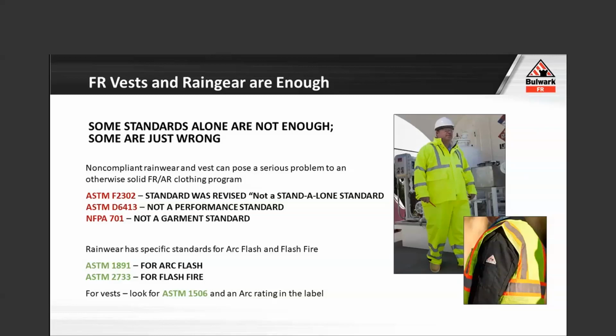There are standards out there that allow manufacturers to claim FR properties that are not a performance standard, and they're not an indicator of how that garment will perform in an arc flash or flash fire. ASTM 2302 in and of itself is a standard that talks to heat resistance and flame resistance, but does not, as a standalone, indicate arc rating or flash fire protection. Combined with other standards, it can, but as a standalone, if that's the only standard referenced in that label, it's not to be used in a flash fire or arc flash environment.